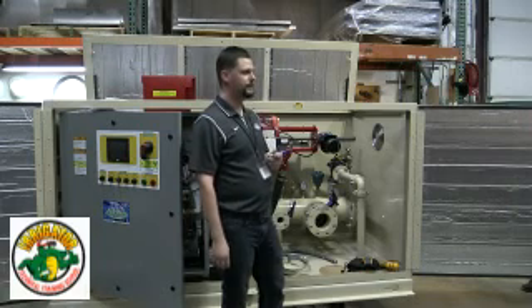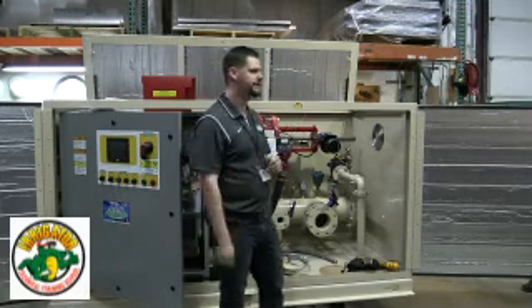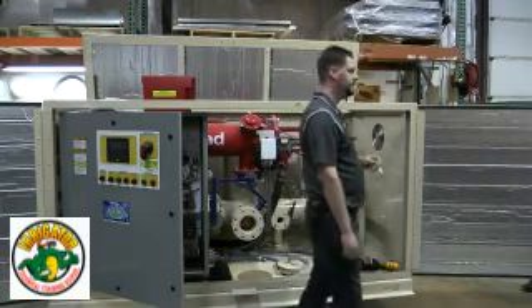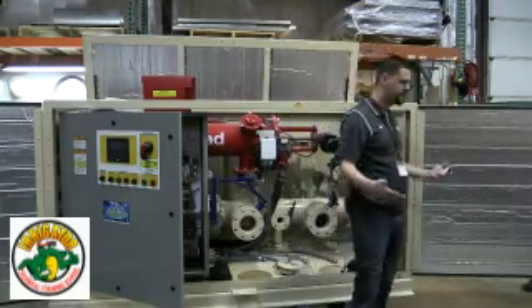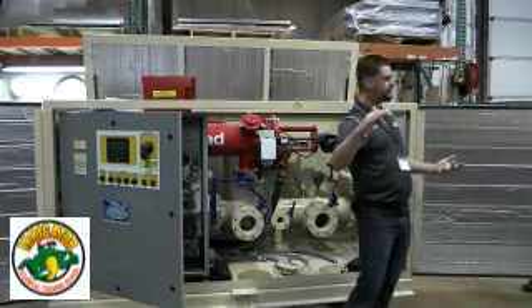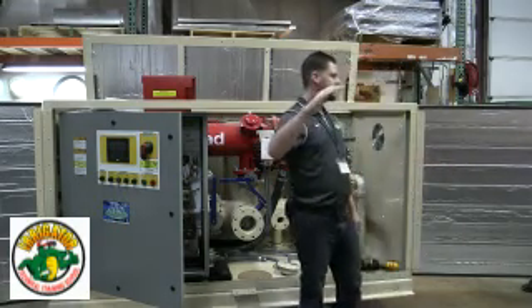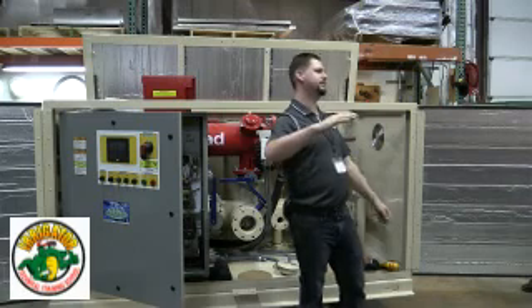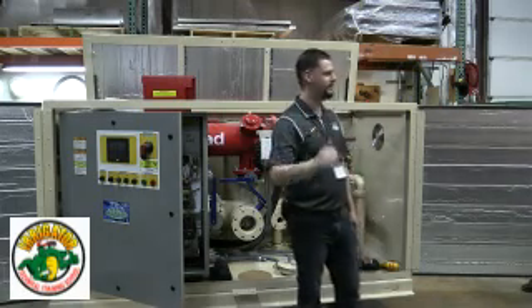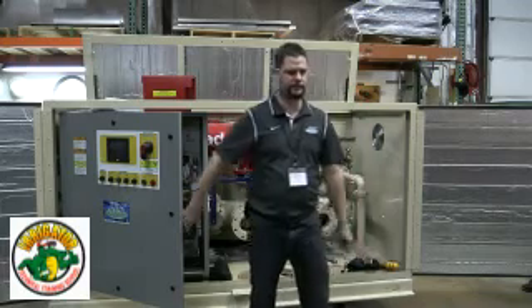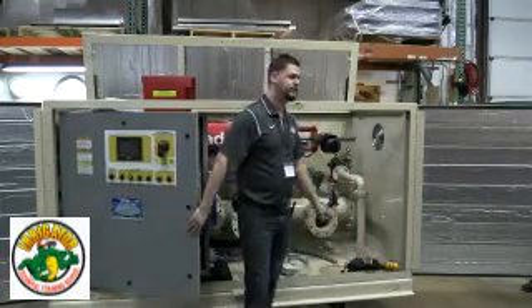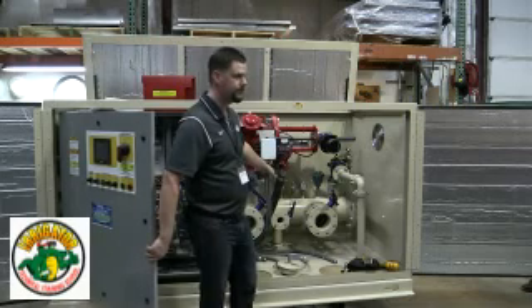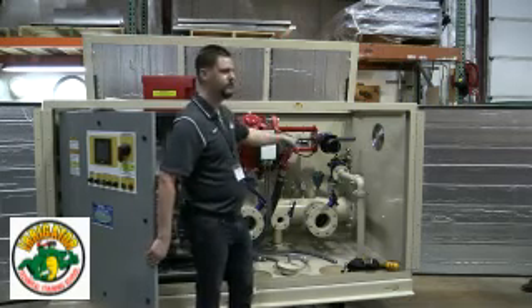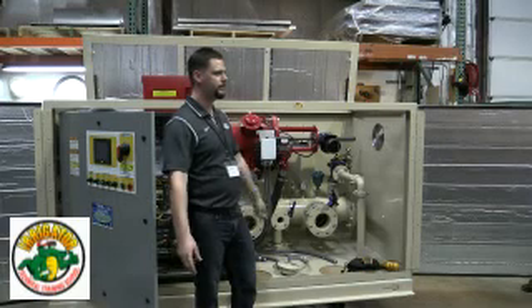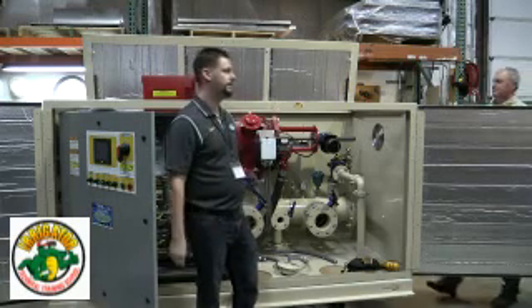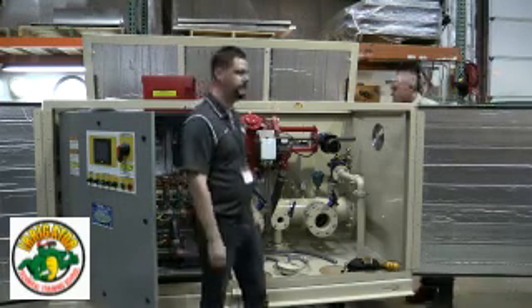What I found with those, and you guys can probably attest to this, they close at a lower pressure. So if you have a 65 pound set point and it opens up at 67 pounds, it'll get down below 67 pounds and then your pumps will kick back on. Well, it's still open, hasn't shut. So that's why you want it about 10 pounds above. Now the reason you want it below the pressure switch is because you want to give that pressure relief valve an opportunity to correct the problem automagically before you shut down the system on high pressure.